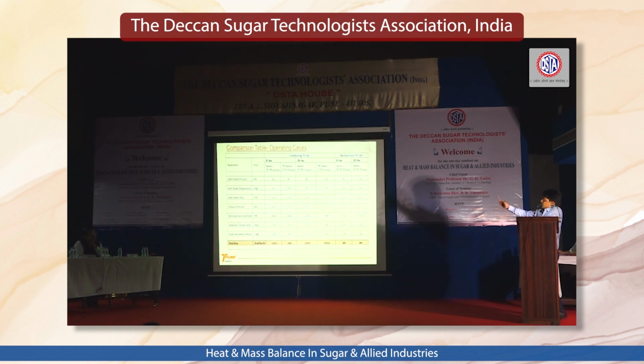Go back to the table. Comparing 85 to 105, and season to off season: in season it is working at 68%, while off season is working at almost 37%, with a heat rate of 2,300 kilocalories per kilowatt hour, giving an efficiency of almost 37%. This is with the regenerative heat cycle. With a non-regenerative cycle, without HP heater and LP heater, considering only the basic deaerator, the cycle efficiency may be close to 29 to 30%.